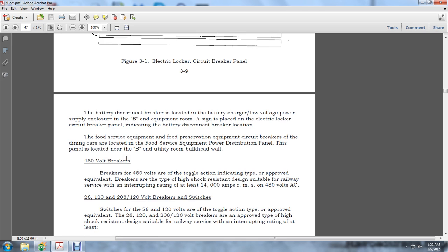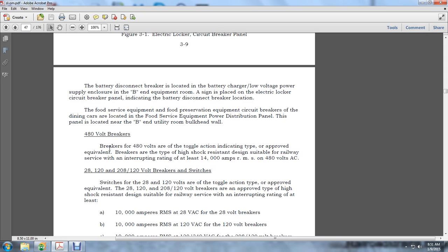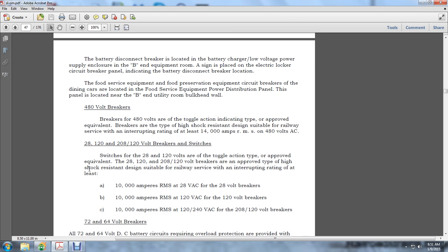The 28, 120, and 208 over 120 volt breaker switches are toggle action or approved equivalent. The 28, 120, and 208 over 120 volt breakers are of high shock resistant design suitable for railway service, with an interrupting rating of at least 10,000 amperes RMS at 28 VAC for the 28 volt breakers, 10,000 amperes RMS at 120 VAC for the 120 volt breakers, and 10,000 amperes RMS at 120 over 240 volt VAC and the 208 over 120 volt breakers.